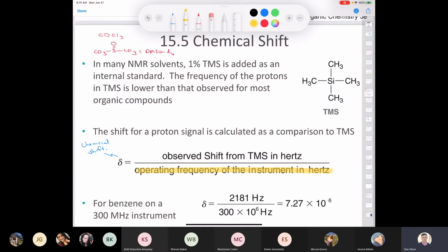That means if I have a low field spectrometer, let's say my magnet has a field that's around 1.4 Tesla, what we said was, well, in order to get the protons to come into resonance, when we have a magnetic field strength, B0, which is around 1.41 Tesla, we need to use electromagnetic radiation that has a frequency of around 60 megahertz, right? Okay, 60 megahertz.